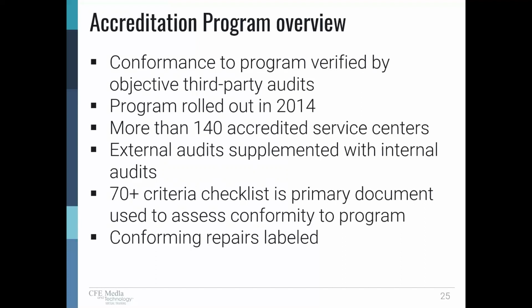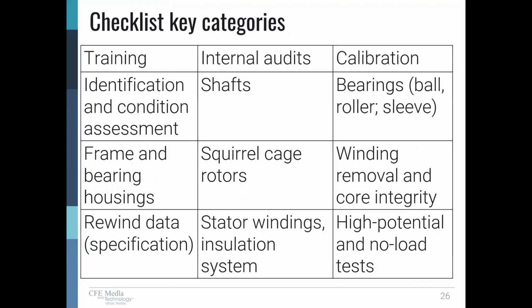And we've got a label that can be put on the motor after the repairs are done. If it's a conforming repair, if it's met all the requirements of the good practices, then it gets labeled as an accredited repair. I'm not going to go through all of these checklist key categories here, but just the top line. It's not directly into the repair, but training. The people who are working on the machines, there has to be evidence that they were formally trained. Internal audits, we mentioned that. Calibration, we mentioned that.